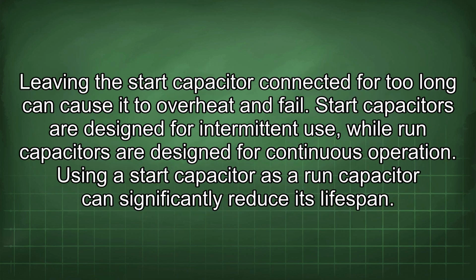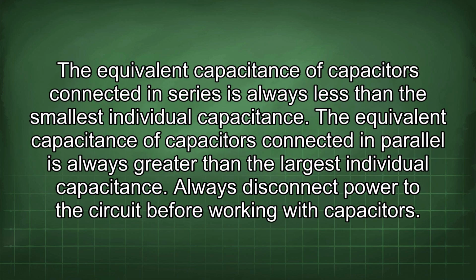Leaving the start capacitor connected for too long can cause it to overheat and fail. Start capacitors are designed for intermittent use, while run capacitors are designed for continuous operation. Using a start capacitor as a run capacitor can significantly reduce its lifespan. The equivalent capacitance of capacitors connected in series is always less than the smallest individual capacitance. The equivalent capacitance of capacitors connected in parallel is always greater than the largest individual capacitance.